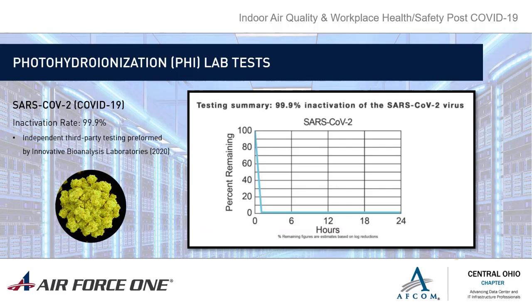One of the interesting things to note is that we have the white paper on the bioanalysis laboratories report, if Michael would like to distribute that. There was a fairly high level of COVID in the test chamber, so it took a specific amount of time. I think the next slide will show that once your inactivation rate is achieved, once the PHI has been in the system and running for X amount of time - a little less than 2 hours here - any reintroduction of the virus is neutralized instantly because it's a very small quantity. The PPM is very small.